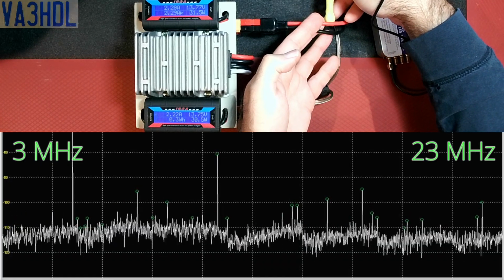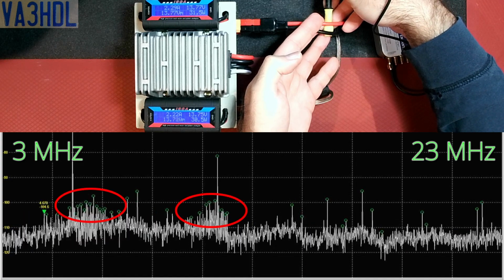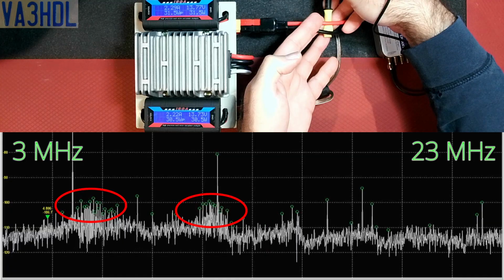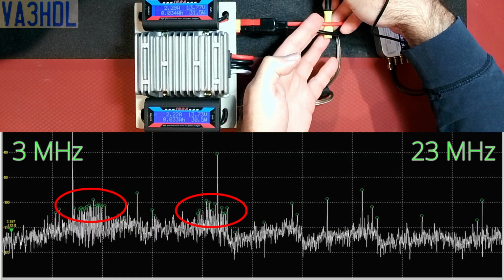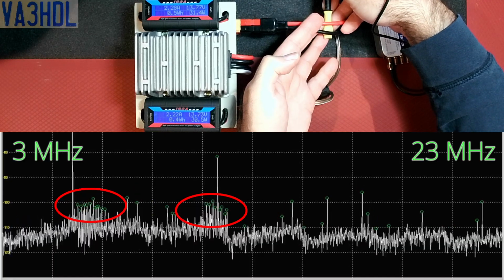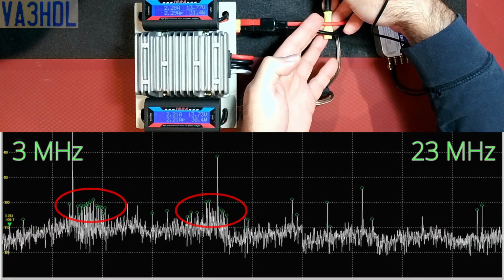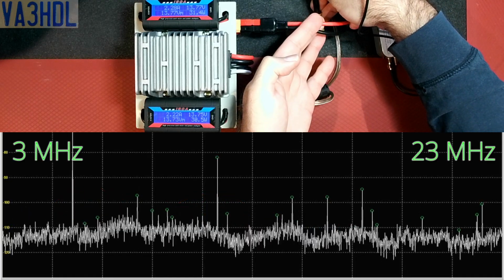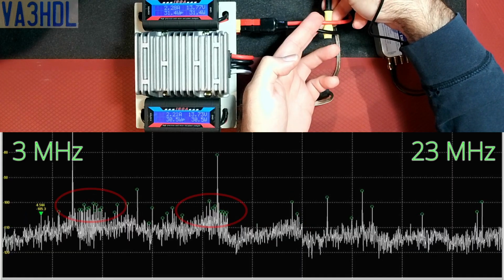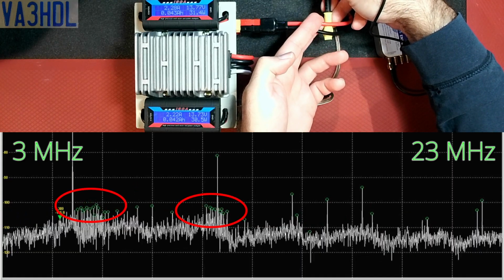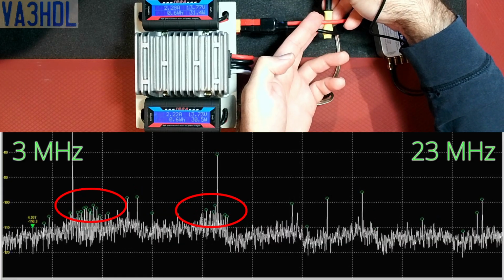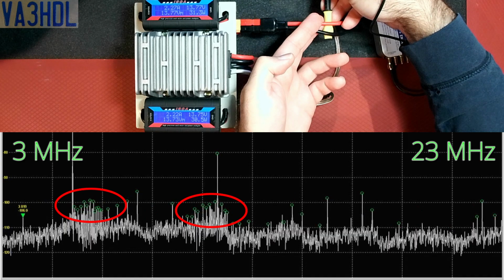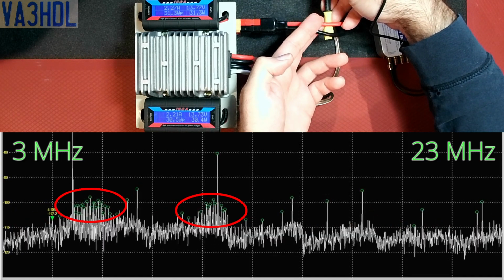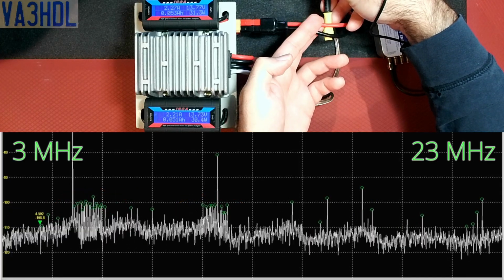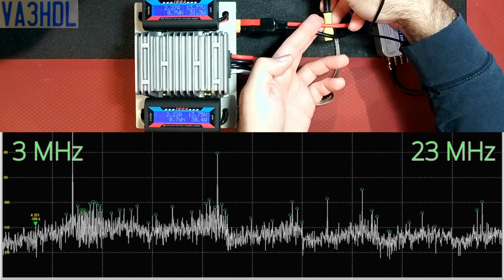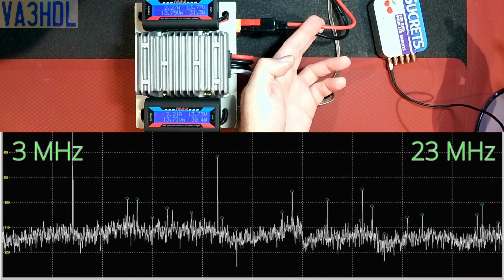We're going to see if the probe is picking up any RFI. As you can see, there is RFI right around 5 megahertz, a big chunk of it. I'm going to take the probe out and bring it back in so you can see the difference. With the probe out, everything goes flat, and when I put it back in, you can see the RFI coming from the power supply feeding this converter, around 5 megahertz. The whole line on the spectrum analyzer drops about 10 dB, maybe a little less, when I take the probe out.